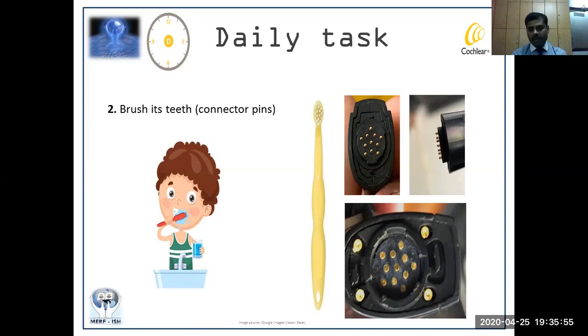Some people might advise cleaning it once a week or once a month, but I would advise you to clean it every day, because if you lose one of these pins, no service can be done—you have to change the entire processor, which costs not less than 2.5 lakhs. So instead of spending 2.5 lakhs, if you spend just 2 minutes every day cleaning those pins, it will definitely increase the longevity and quality of the device, and also reduce your overheads.